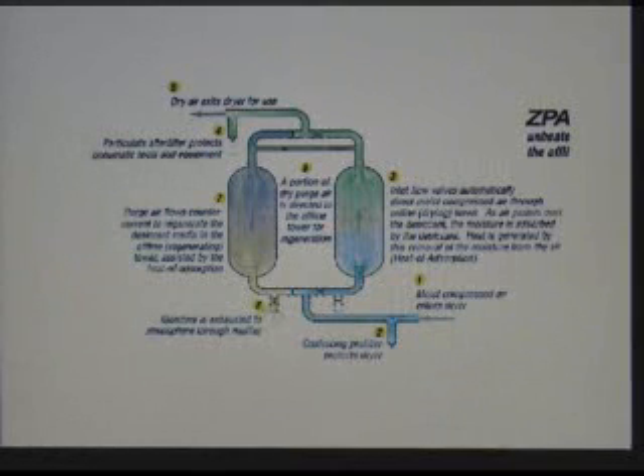This is how it works. Moist air comes in, gets trapped in the desiccant, and then the purge air will come along and purge the water out so that the desiccant becomes dry again, ready for use when the first tower starts to get saturated. The amount of purge air depends on the process of the desiccant that's being used.